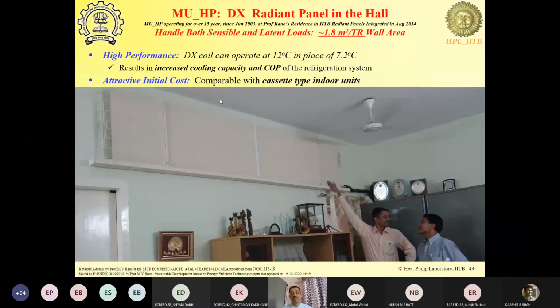Typically, the conventional panel radiant heat exchangers require about 20 to 40 meters square per ton because they can't handle condensation. You need precise control of temperature and humidity also and things like that. But in our case, we don't have this, and this is a DX system.